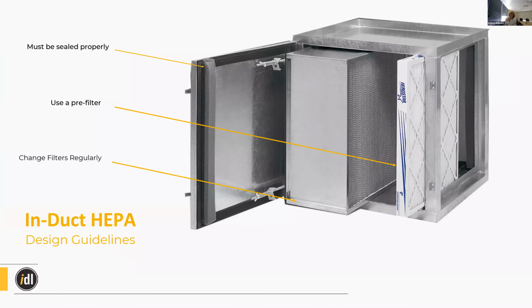For in-duct HEPAs, it doesn't make a lot of sense to retrofit your HVAC to accommodate them, just because there is such a high pressure rise associated. Your fans have to work so hard to push air through that really fine folded mesh of the HEPA filter. So if your HVAC isn't rated for that, your fans are going to blow out, and you're just going to have to replace those and such. Another reason that it would be hard to retrofit for an in-duct HEPA filter is because of the leaks associated.